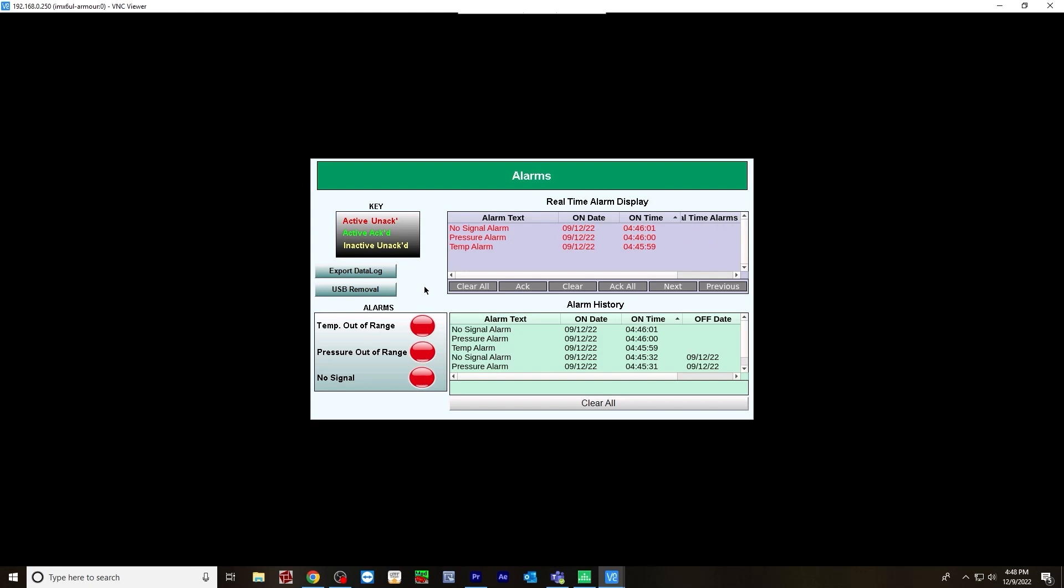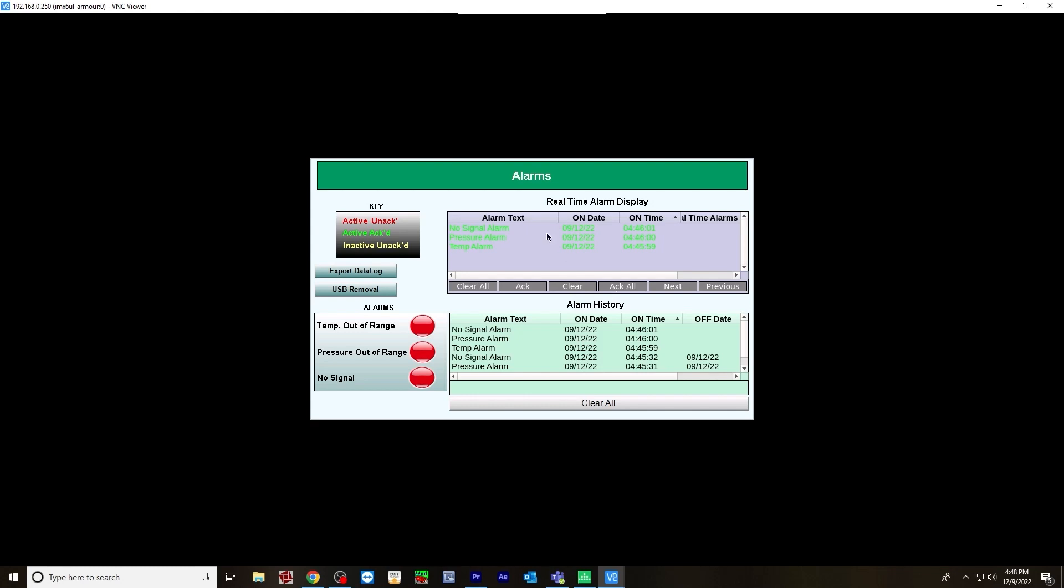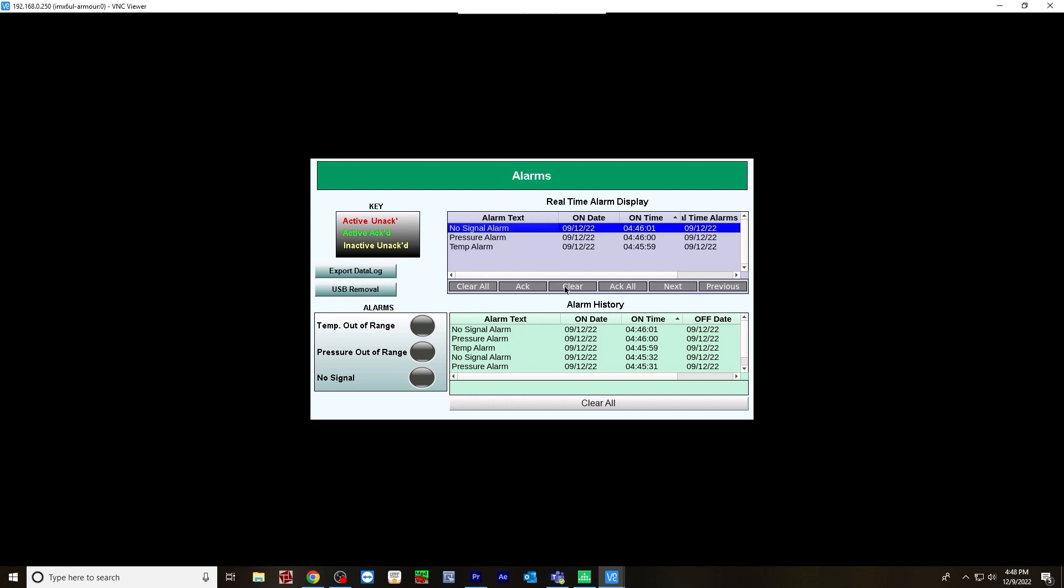Let's trigger them again. They're red again. Now let's acknowledge them. You can either individually acknowledge them - if you click one, hit acknowledge, it's green. Or you can just acknowledge all. Now they're all acknowledged. In order to clear the alarms, you'll need to turn off the alarms here, and then either select one individually and hit clear, or you can just hit clear all. And they're gone.